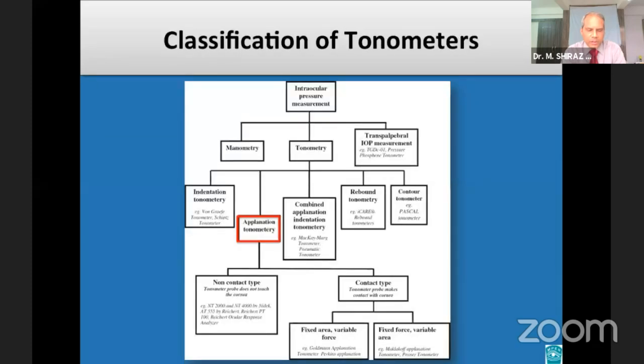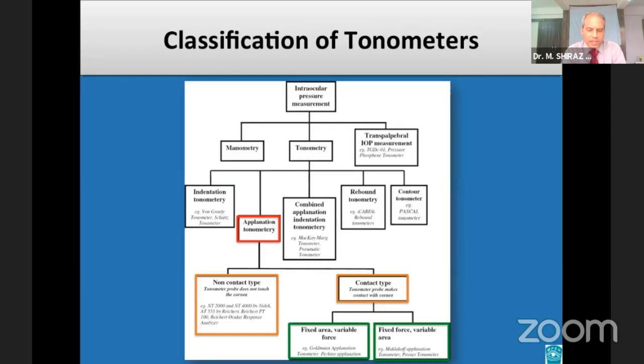Coming back to the classification, the most commonly used applanation tonometers can be of two types: the non-contact types and the contact types. The contact types are further differentiated on the basis of the variable that is measured. Fixed area, variable force tonometers measure the force required to applanate a standard area of the corneal surface — the prototype is the Goldman applanation tonometer. Fixed force, variable area tonometers measure the area of the cornea flattened by a known force — the prototype is the Maklakov tonometer.